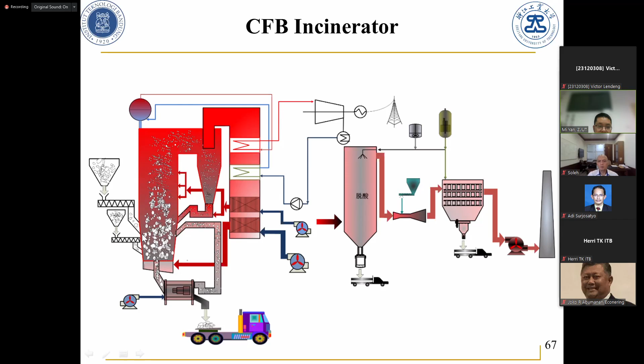And this is the CFB structure. So here is the bed, with the air distribution board, this is the ignition, and the primary air comes from here, and this is the feeder of the waste, and this is the furnace, and the membrane heat exchanger, and this is the cyclone. In the grate, we don't have a cyclone. Only the CFB has a cyclone. The cyclone is just used to catch big particles of the ash. So the ash will come back through this loop seal, making cycles. So the ash comes back, then the flue gas goes out to the heat exchangers. So this is the evaporation equipment. This is for primary air. So this is for superheat, and primary air preheat and economizer.